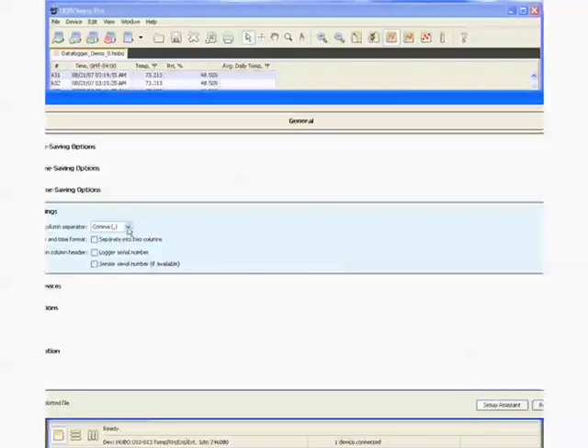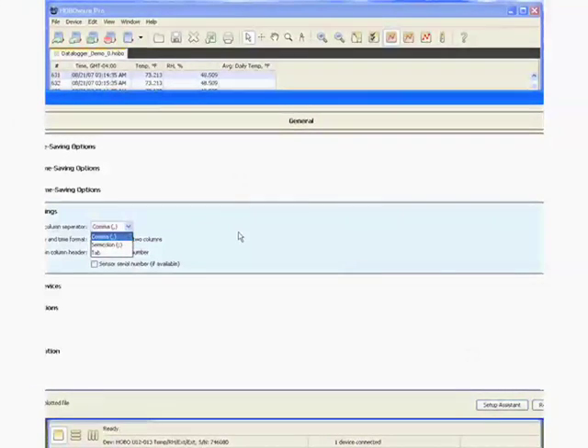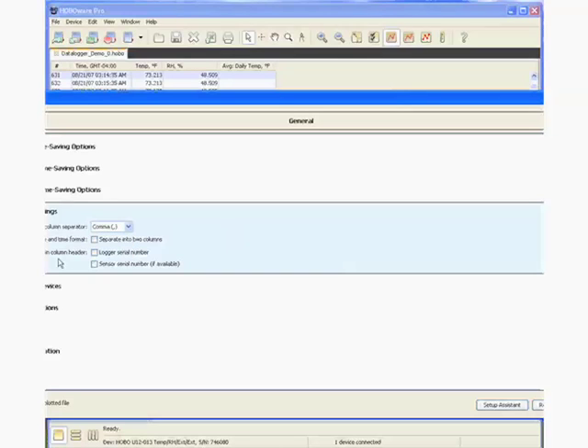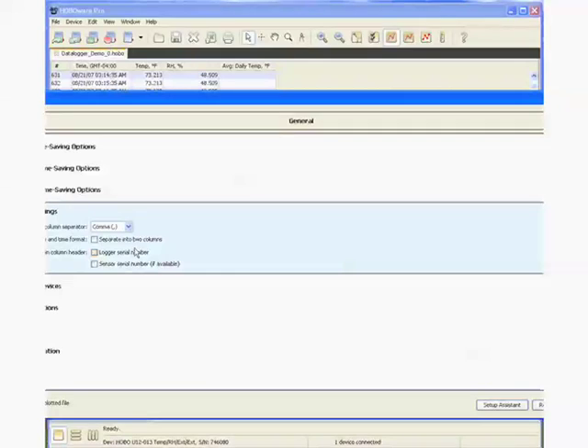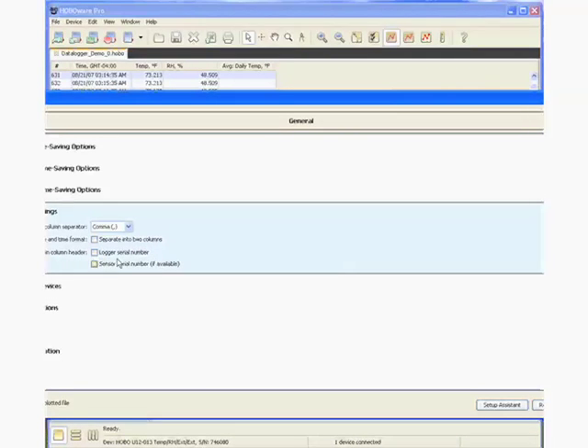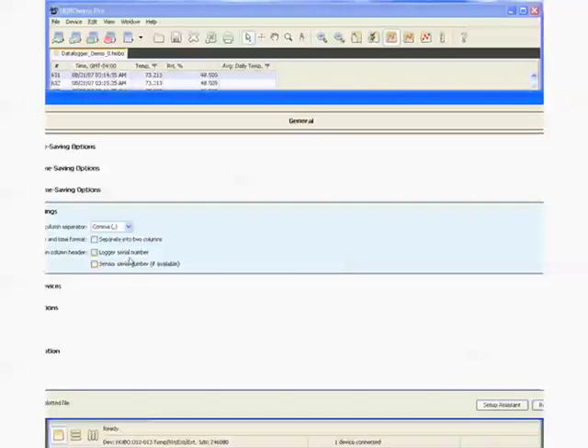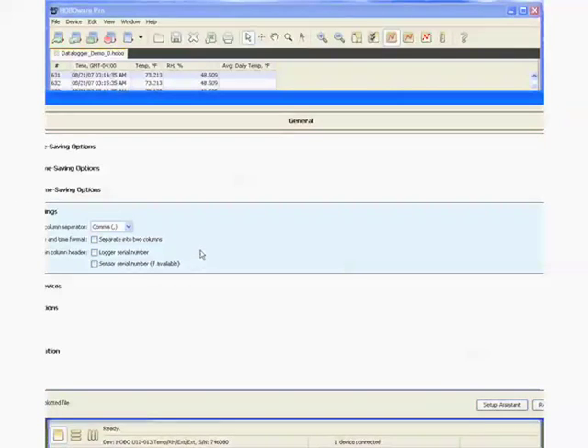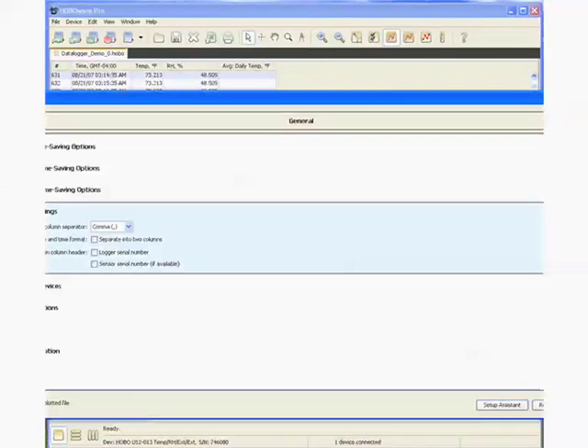Basically, you can select comma, semicolon, or tab separated variable. You can set up the time and date format to be in separate or a common column. And you can include in the column header or exclude the logger serial number and the sensor serial numbers if they are smart sensors, which is a different product than what we're talking about today.